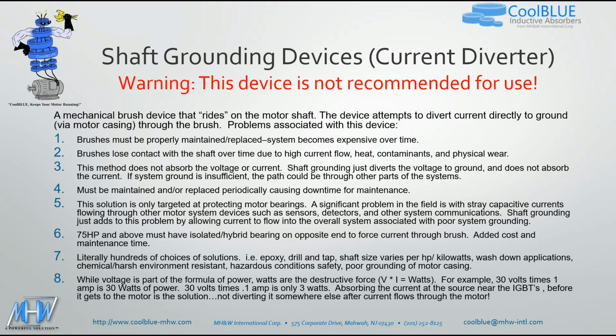For the first solution, which is a shaft grounding device or current diverter, it's a mechanical brush that rides on the motor shaft. This device attempts to divert the current directly to ground via the motor casing through the brush. Unfortunately, there's a whole series of problems associated with this type of device. First, brushes must be properly maintained and replaced, and the system can become expensive over time. The brushes lose contact with the shaft over time due to high current flow, heat, contaminants, and physical wear. This method does not absorb the voltage or current. The shaft grounding just diverts the voltage to ground and does not actually absorb the current.